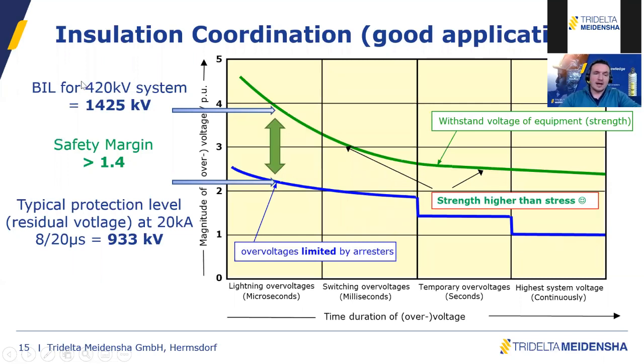Typically, the BIL is the lightning impulse insulation level of the equipment. For a 420 kV system, a typical value is 1,425 kV. If we take a surge arrester rated 360 kV, the protection level, the residual voltage of the arrester at the nominal current of 20 kA, is 933 kV. With such a configuration, you have a safety margin higher than 40%, which is the recommendation by IEC.